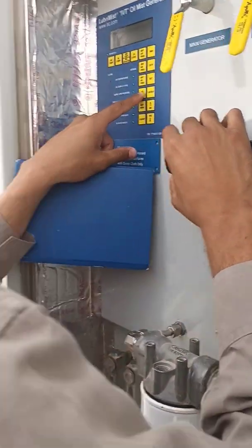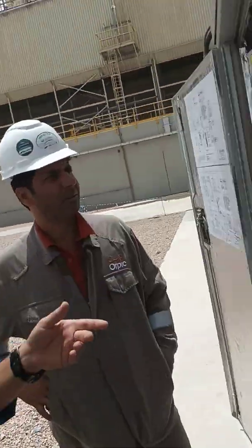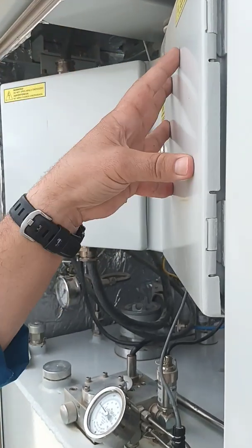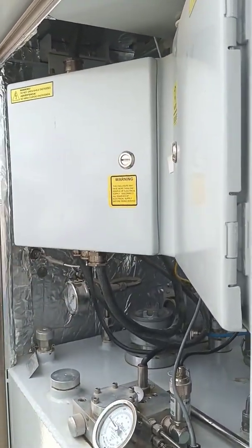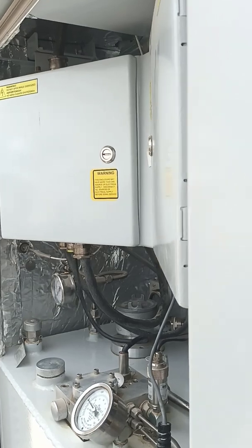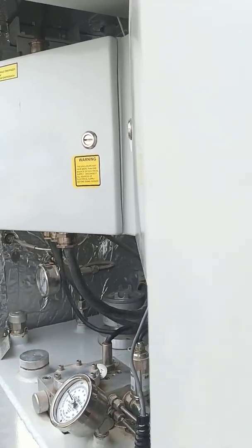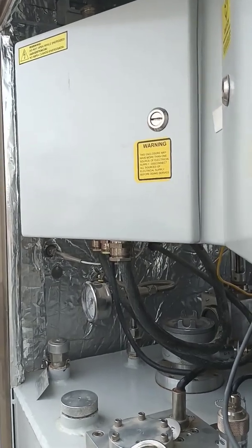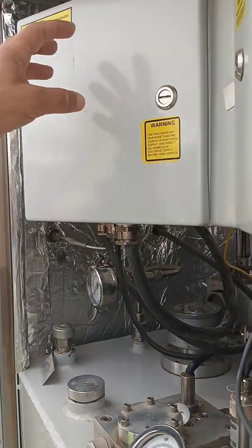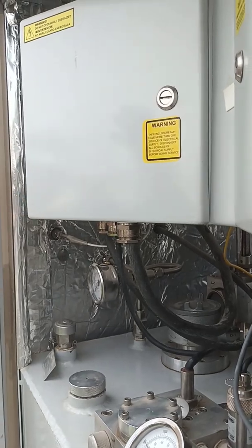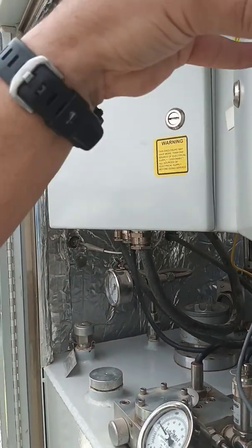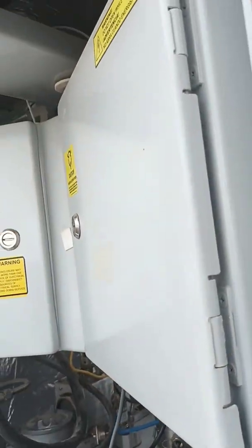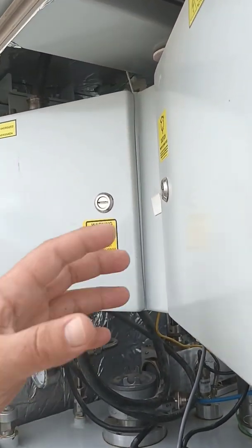These two boxes here, you got the power supply for the machine. You got AC power and DC power. So the motherboard is here. Here you have all the fuses and all the AC power, which is for the air heater. Basically, the air heater is only this AC power. The DC power is 24 volts. Here you have the transformer, and then 24 volts is coming here. And all the accessories, all the sensors are coming here. So the motherboard, the controller is on this side.